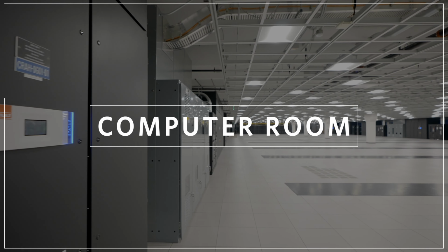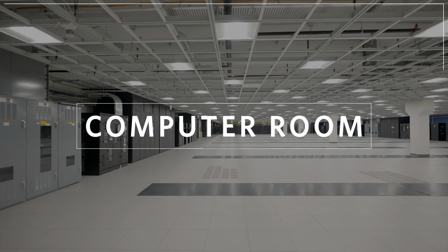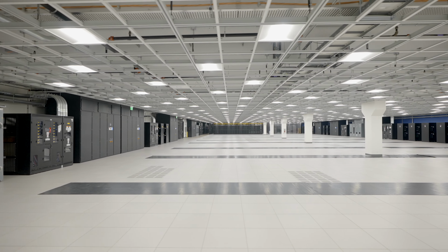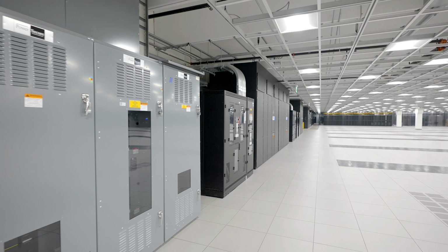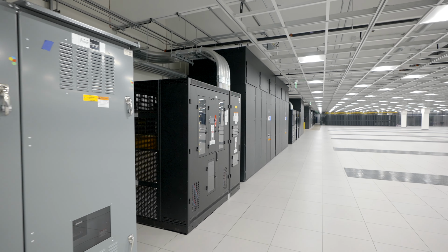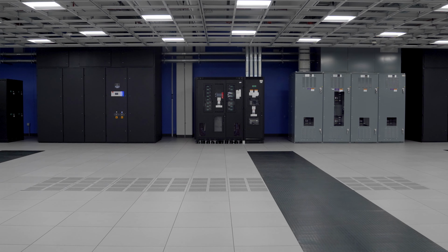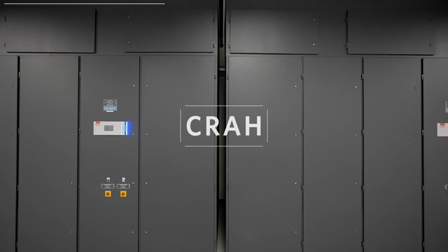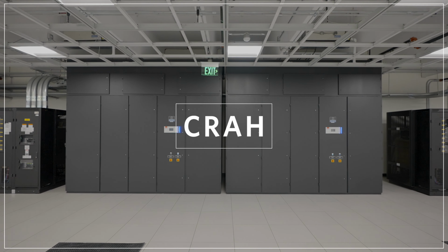Here we go into computer room OG01, which is a 35,000 square foot data center space that has been designed to support up to 6 megawatts of total IT draw. This computer room was built with a 36-inch raised floor and 5-foot overhead return air plenum. Cabinets are placed in rows with all equipment facing interior cold aisles, and cooling is supported by CRAH units placed on the perimeter of the room for maximum allowance of cabinet space and underfloor airflow.